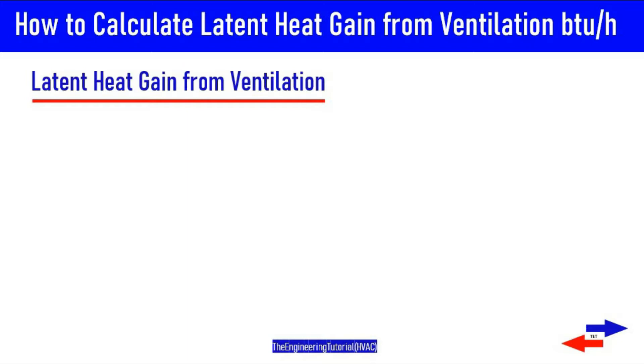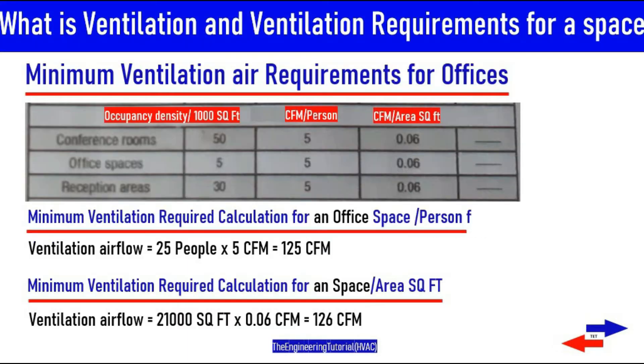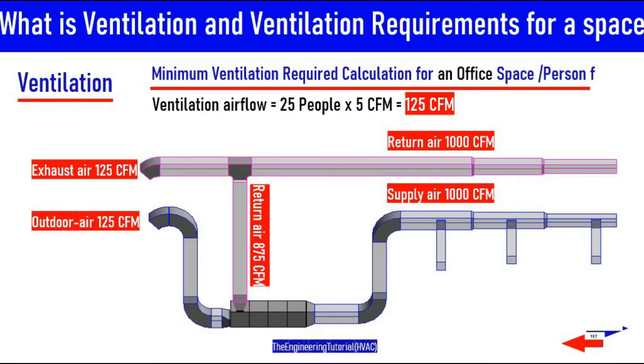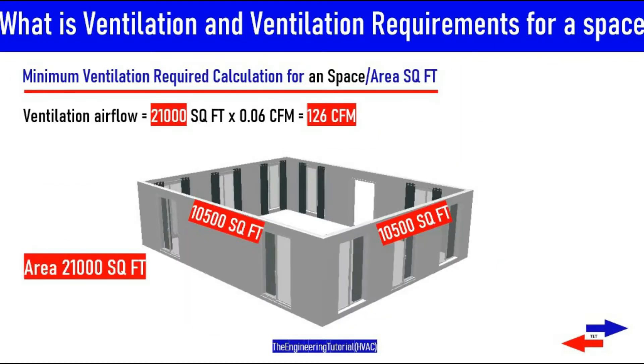The topic of this video is latent heat gain calculation from ventilation. In the first part, we discussed minimum ventilation calculation and ventilation requirements based on CFM per person, CFM per square feet, and CFM based on occupancy density per 1000 square feet. We used two methods: the first method gave us 125 CFM of airflow for 25 people, and the second method gave us 126 CFM for an area of 21,000 square feet.